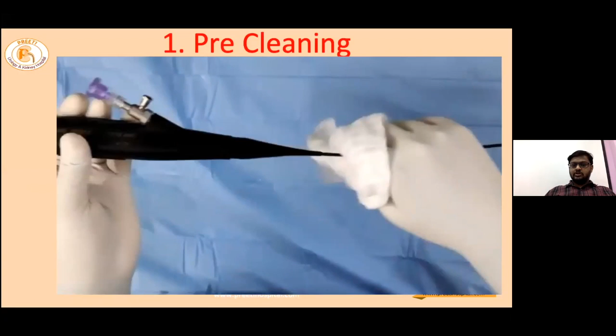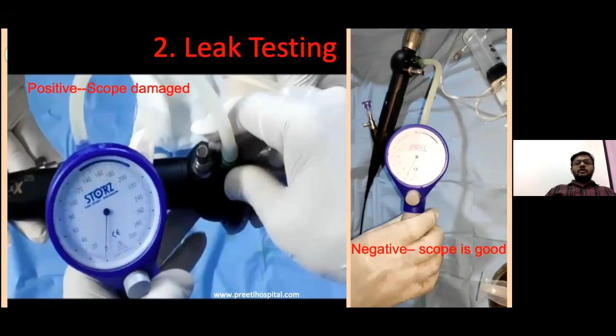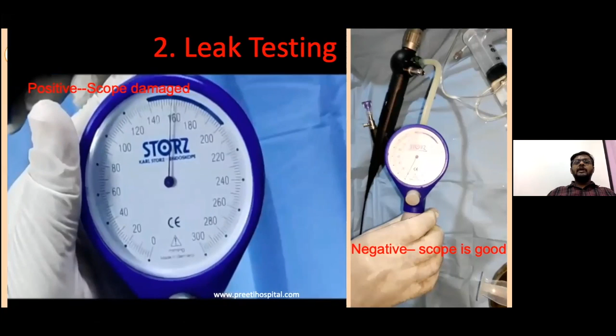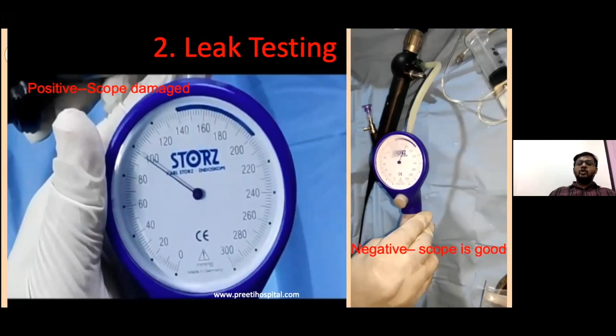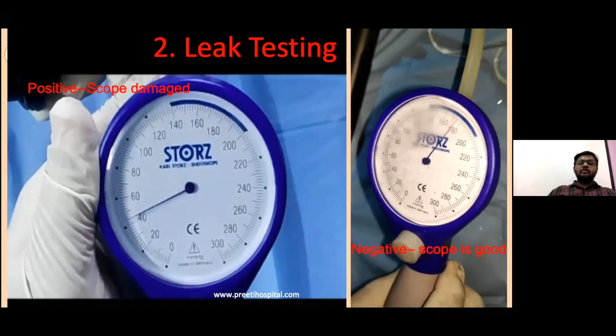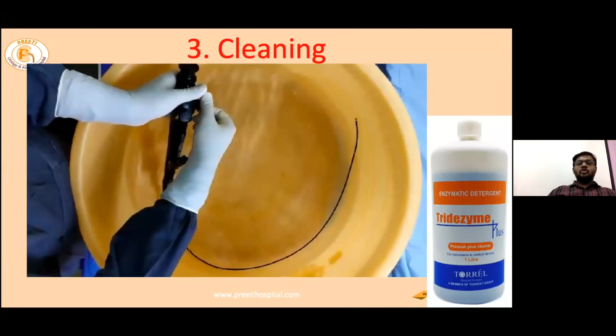After cleaning the scope, the main aim is to check whether the scope is leak-proof or not. These are the 2 scenarios. The first one is a positive leak test, where the scope is not able to maintain the pressure. In the second scenario, the scope is able to maintain the pressure, meaning the scope is good. In the first case, the scope has a leakage in the flexible channel. We can confirm this when we put it in water, we can see air bubbles from damage caused by the laser fiber. Once the scope is leak test positive, it goes directly to the manufacturer for repair. When the leak test is negative, we take the scope for further cleaning.